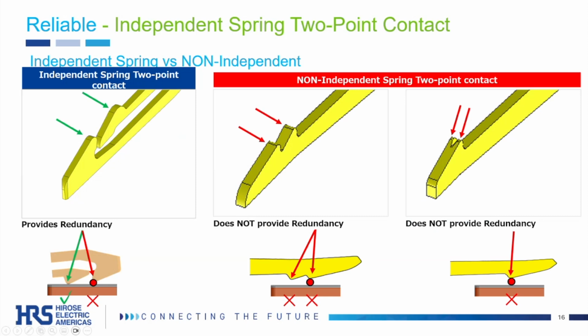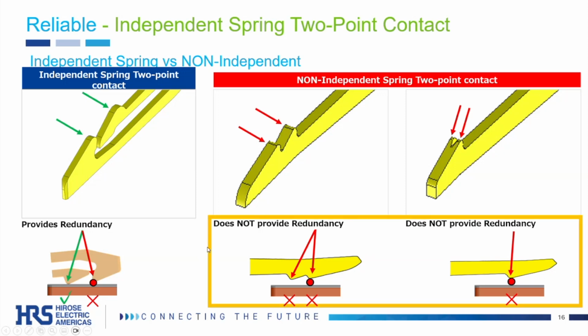And let me explain why we are careful to say independent spring. It clearly distinguishes ours from the non-independent two-point contacts offered by some other suppliers, which do not provide real redundancy. As you can see here, when something gets between the contact point and the terminal, the whole terminal is lifted. So the other contact point is disconnected at the same time. Two contact points on paper, but only one in reality.